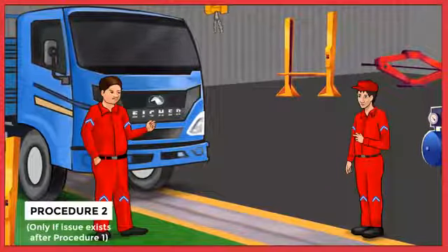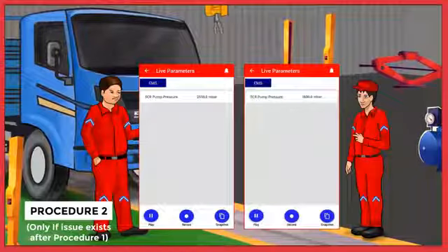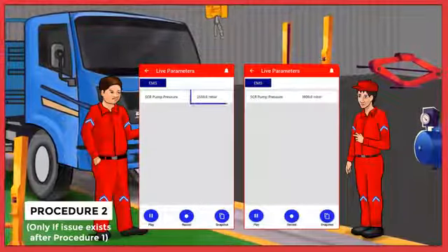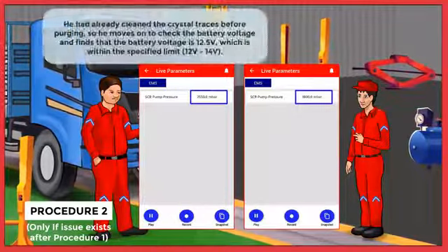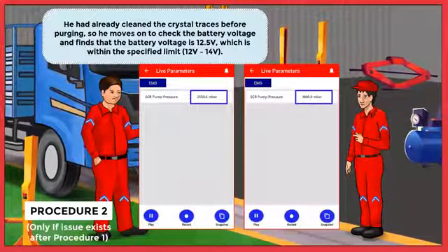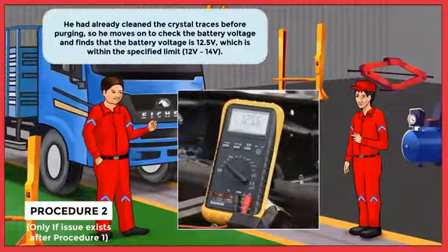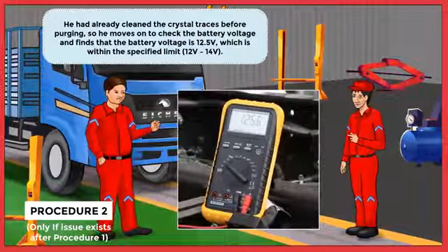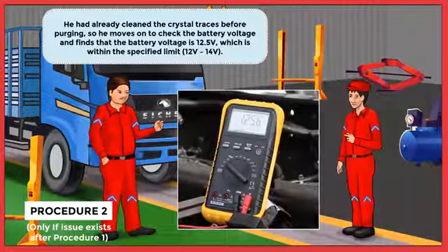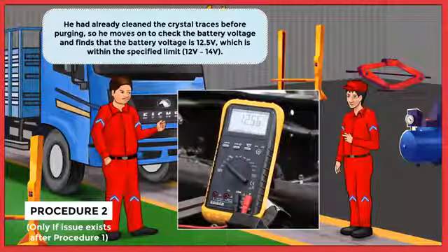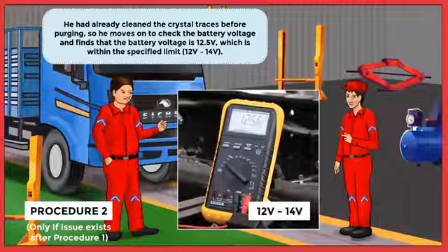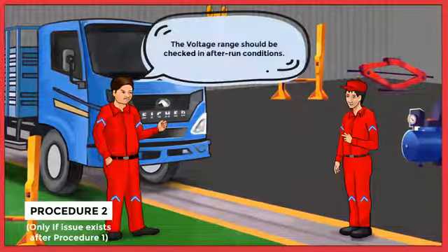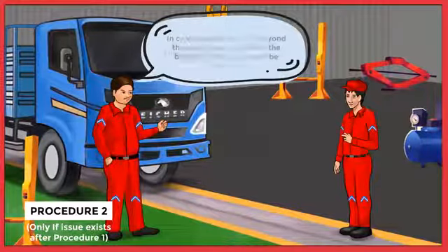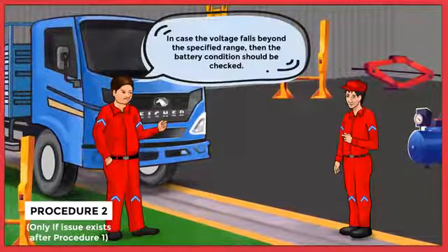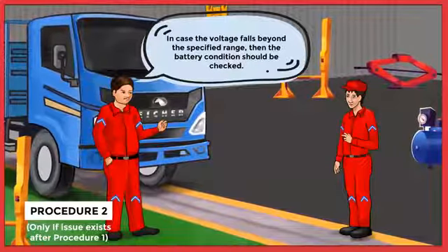The technician then moves to procedure 2 of the troubleshooting guideline, as sufficient amount of pressure is not building up in the pump, even after priming and purging. He had already cleaned the crystal traces before purging. So, he moves on to check the battery voltage, and finds that the battery voltage is 12.5 volts, which is within the specified limit, that is between 12 to 14 volts. Note that the voltage range should be checked in after-run conditions. In case the voltage falls beyond the specified range, then the battery condition should be checked.